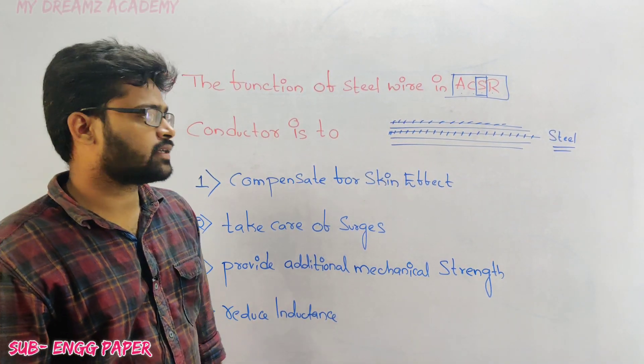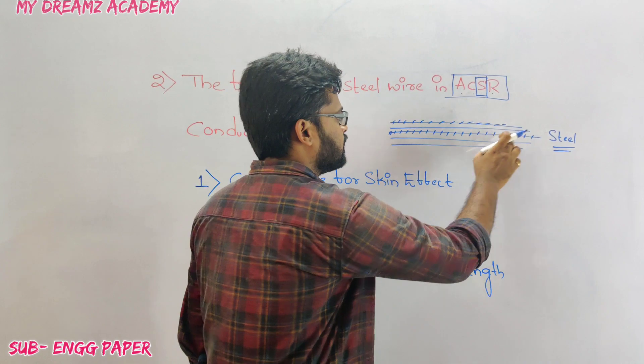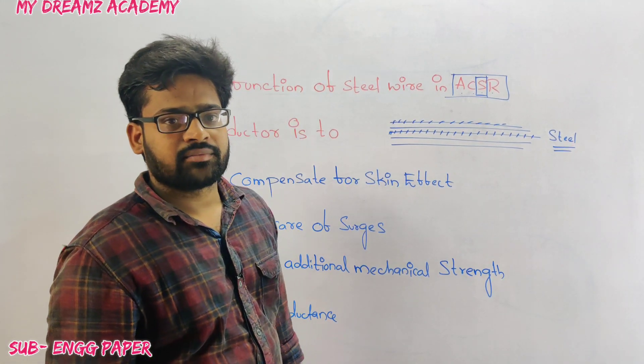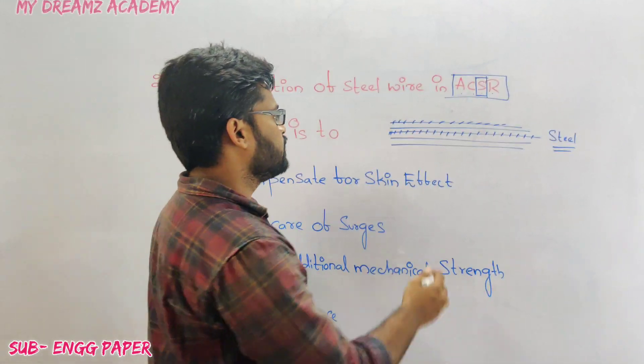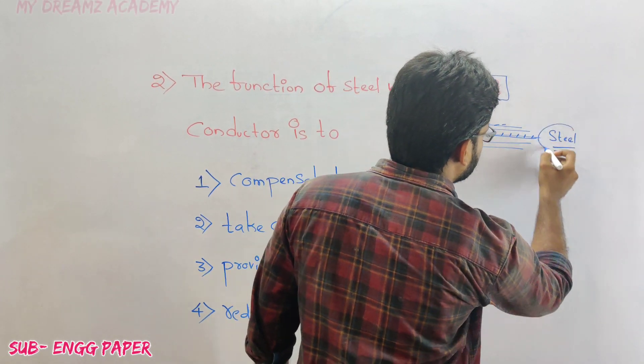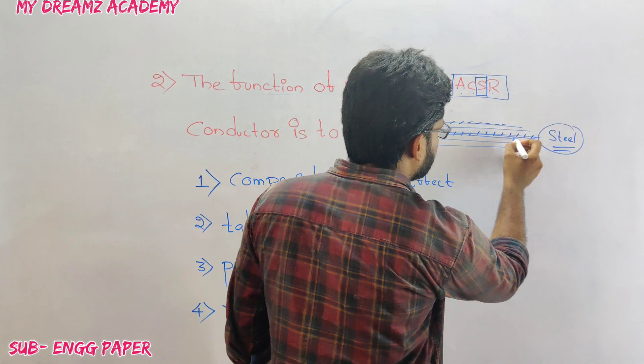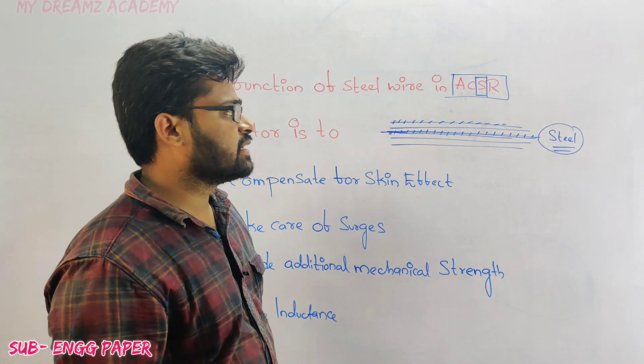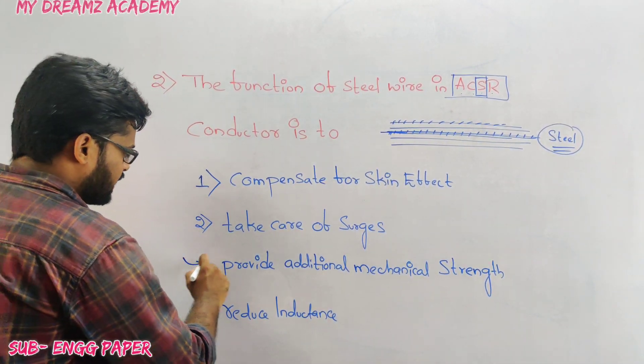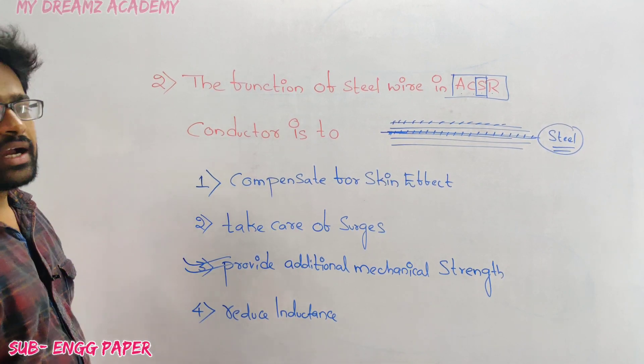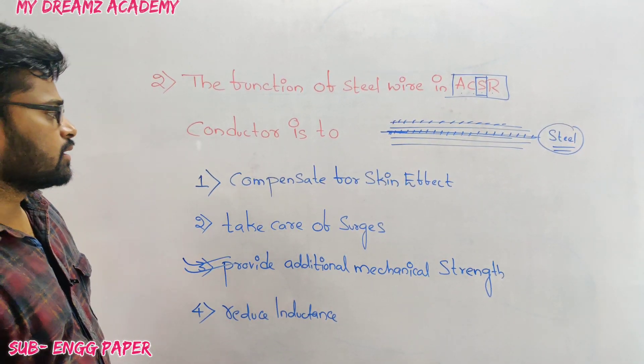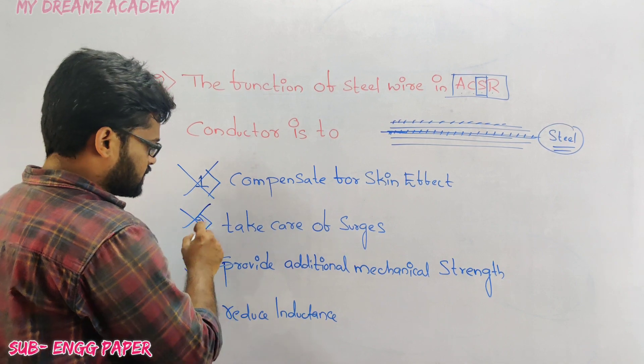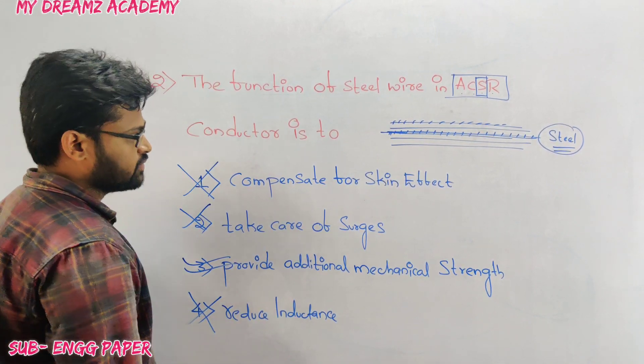Due to skin effect, the current density is high at the surface of the conductor and very less at the inner layer. So if you use aluminum at the center it will be a waste of cost, so we use steel instead. Another advantage is that the steel provides additional mechanical strength to the conductor.